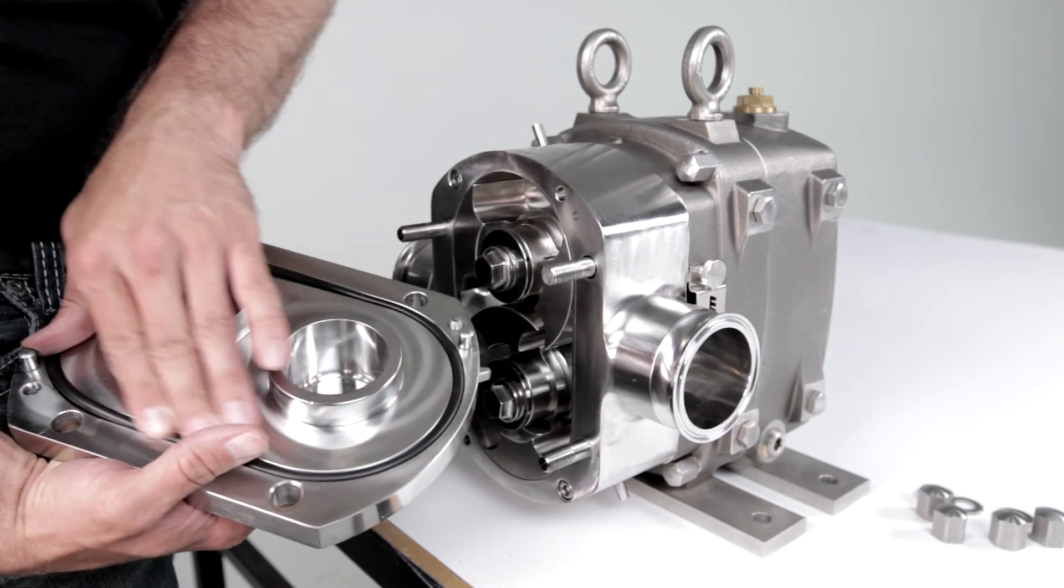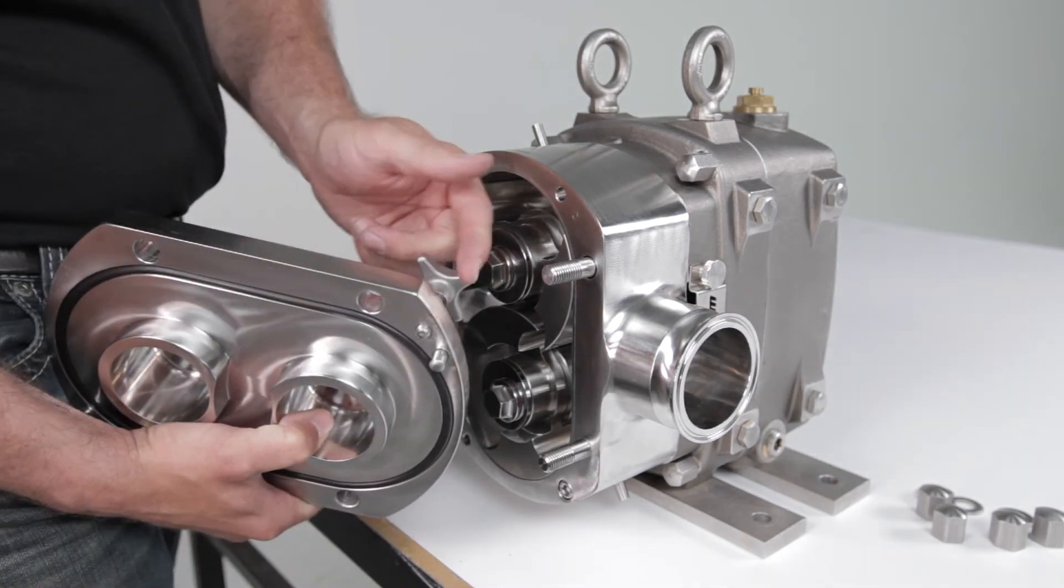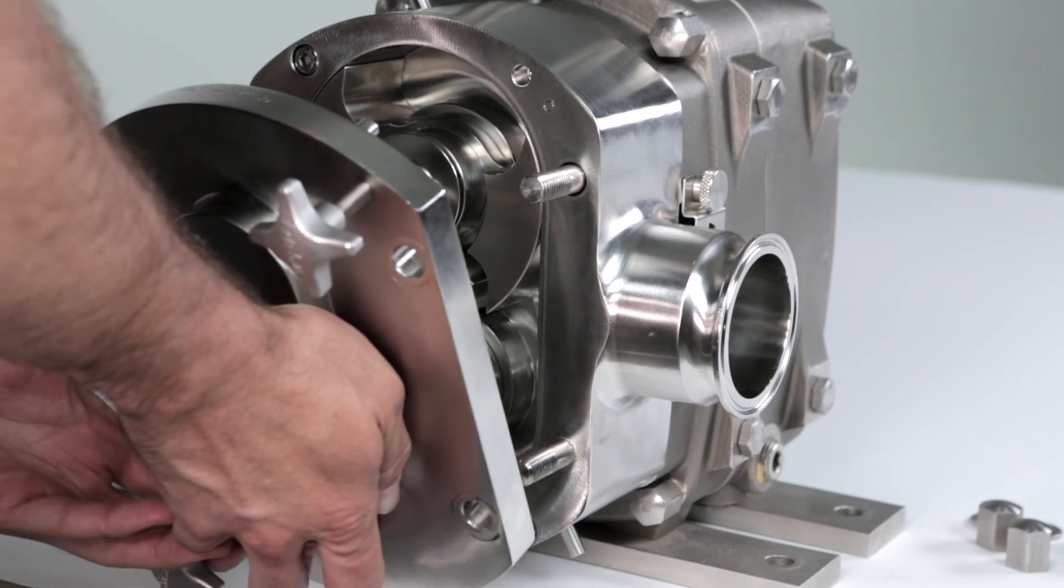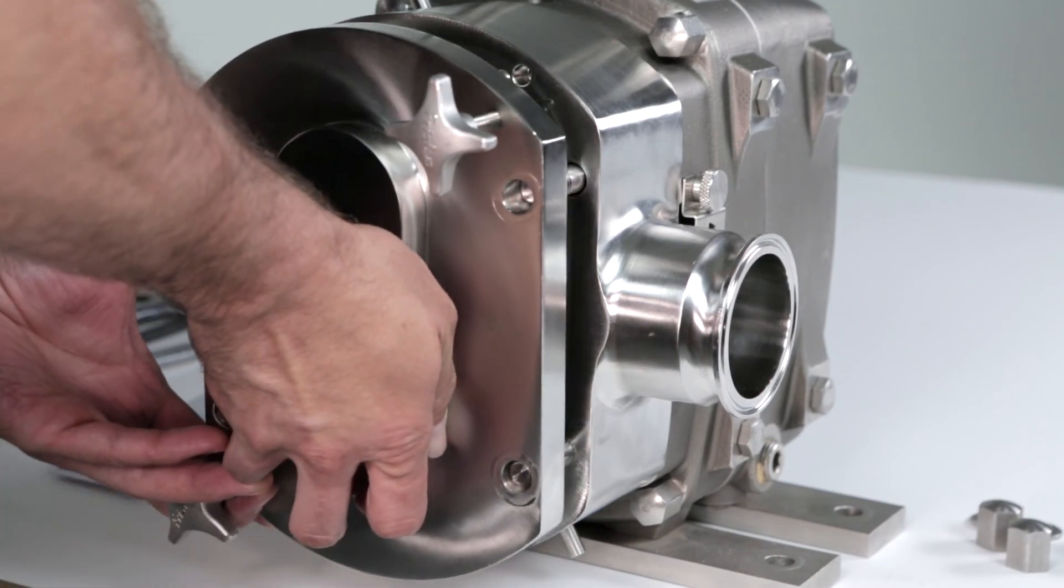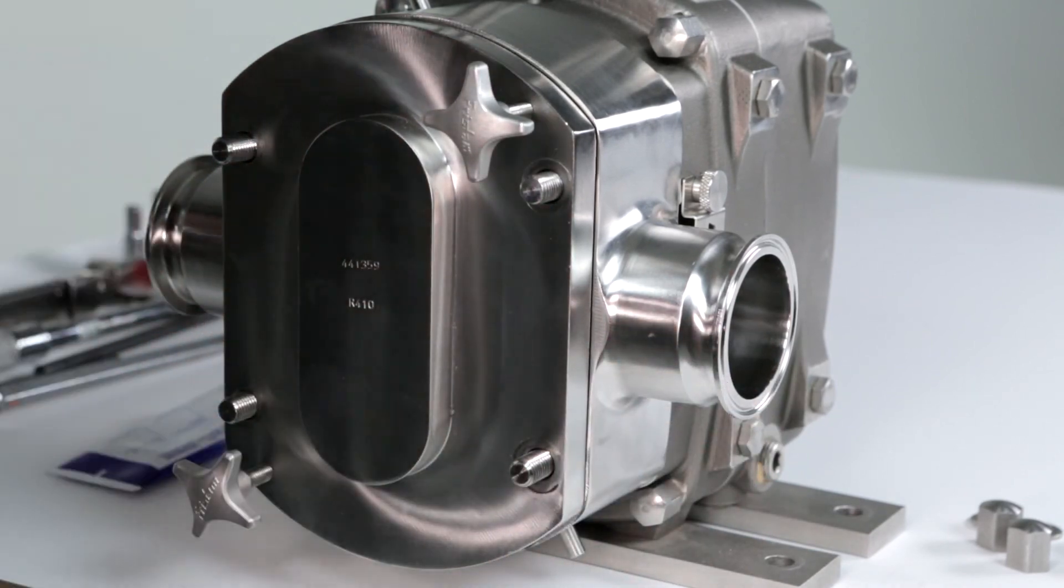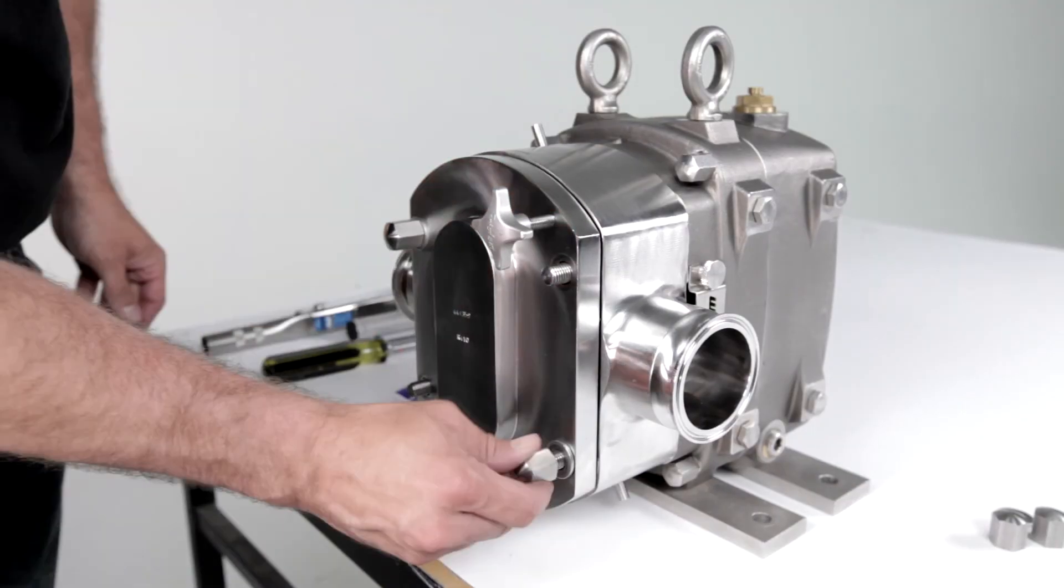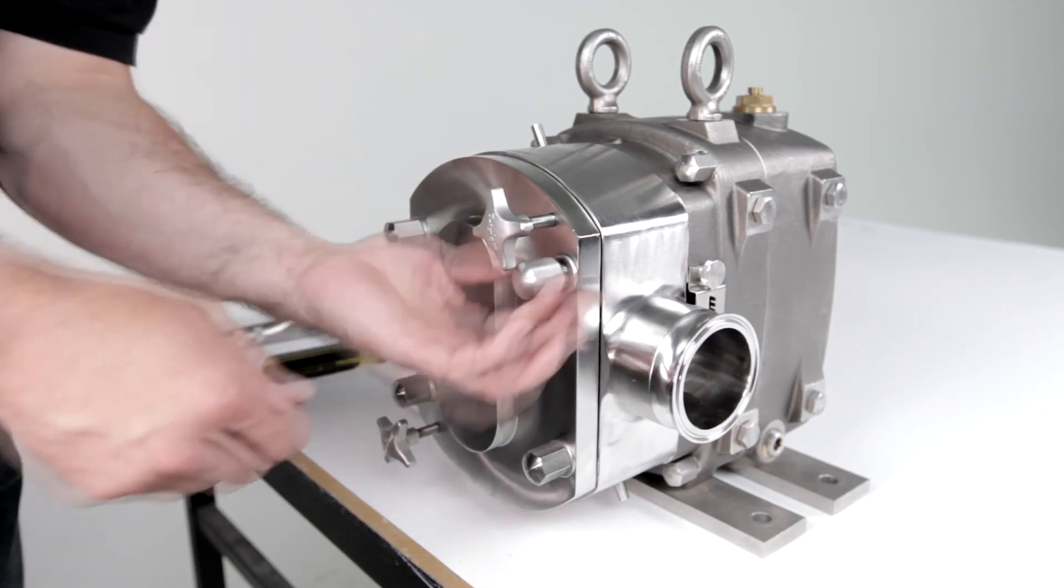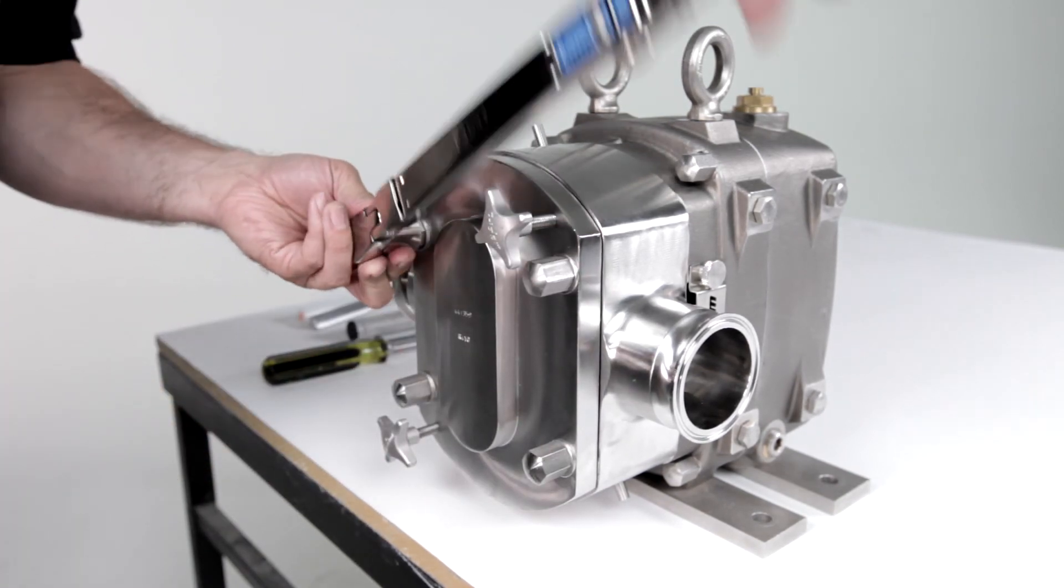Install the cover o-ring onto the cover. Ensure that the cover forcing screws are backed out. Carefully slide the cover onto the housing with the serial number facing up to match the position on the housing. Install cover nuts and cover nut washers. Use a torque wrench to tighten the cover nuts.